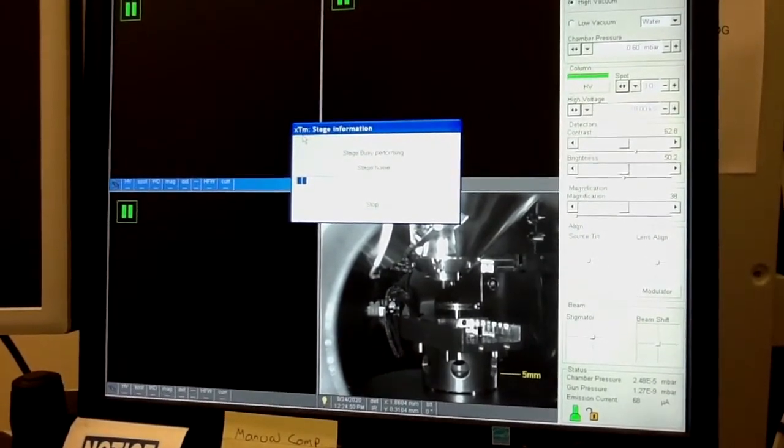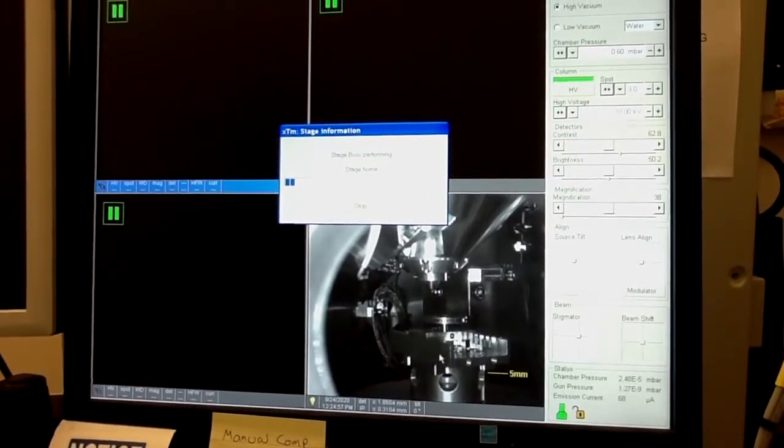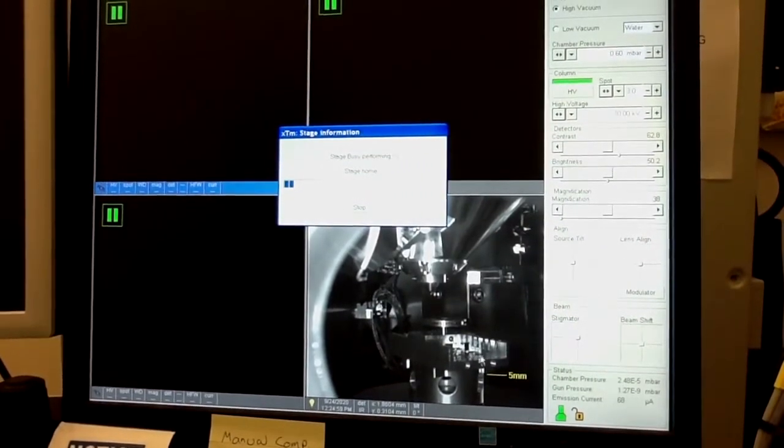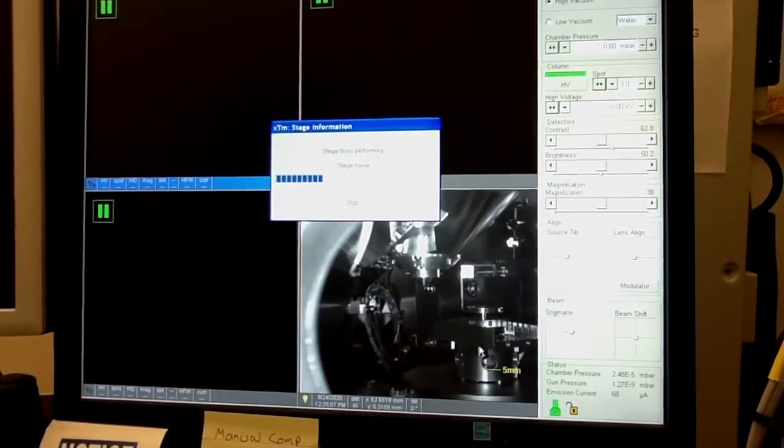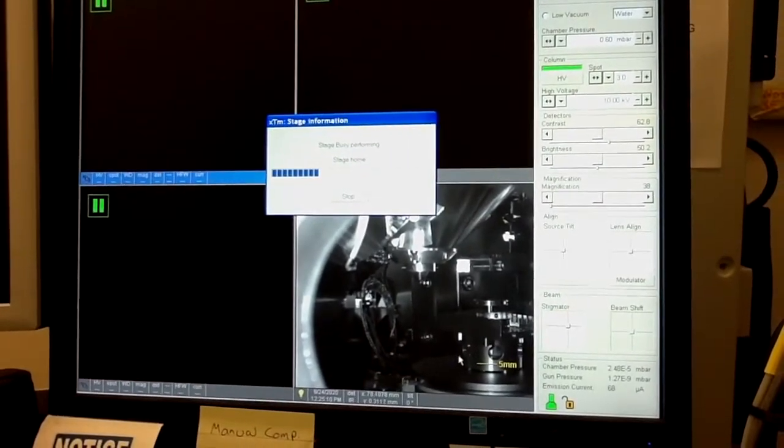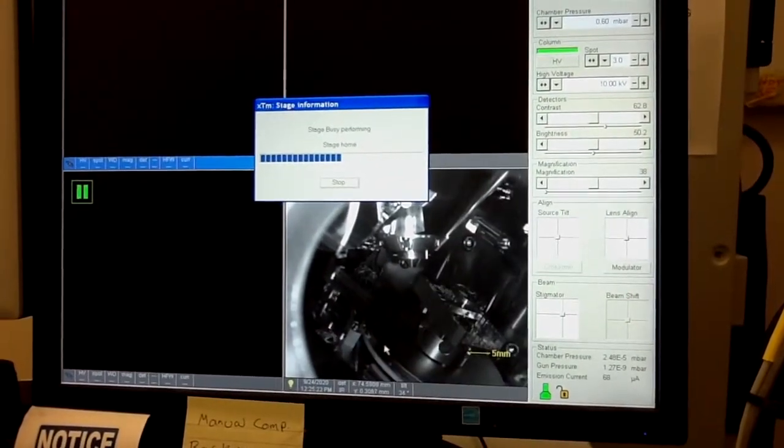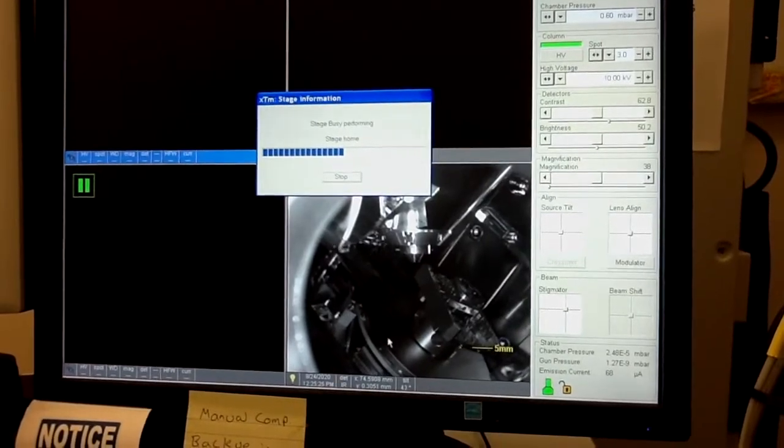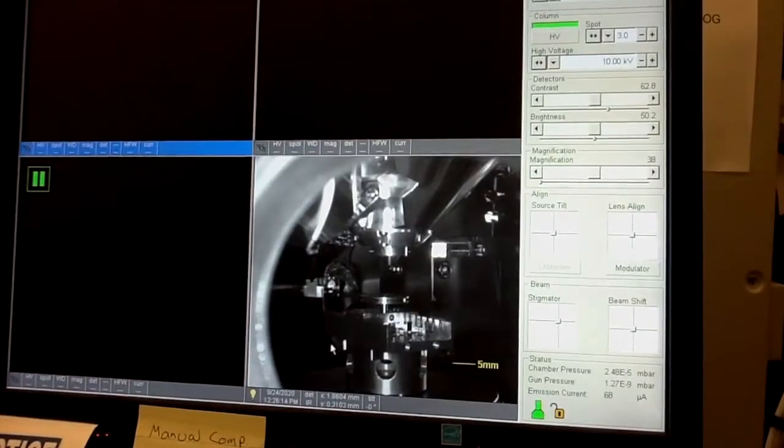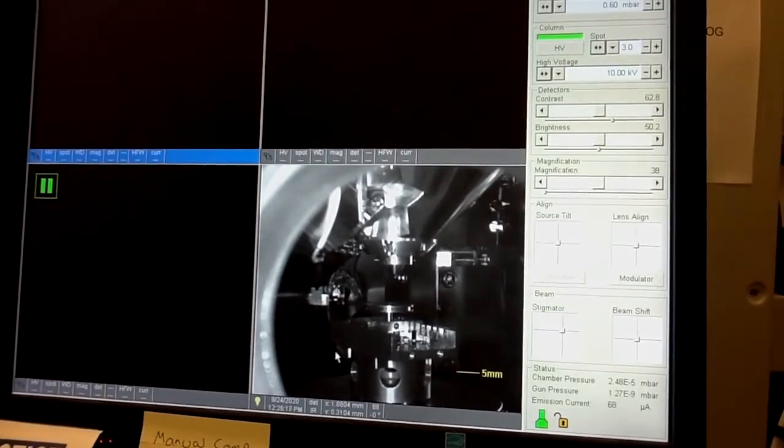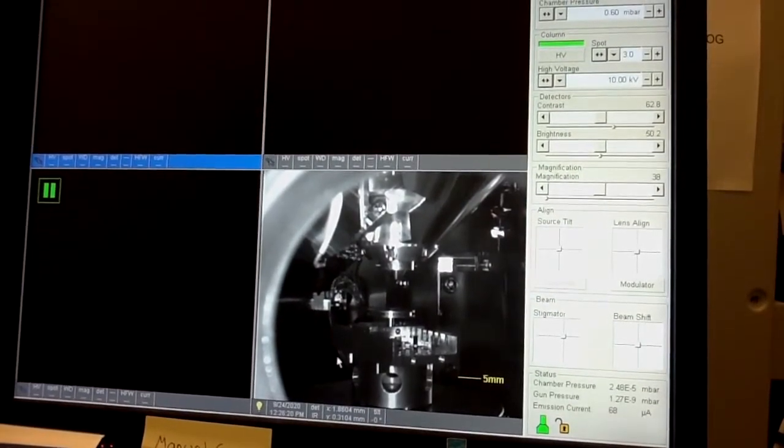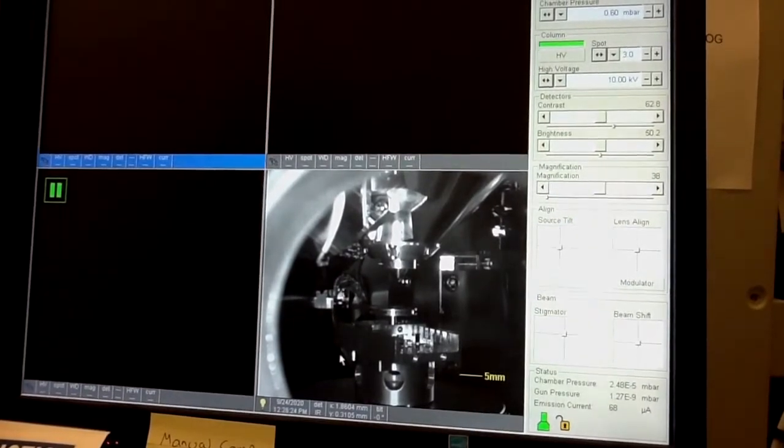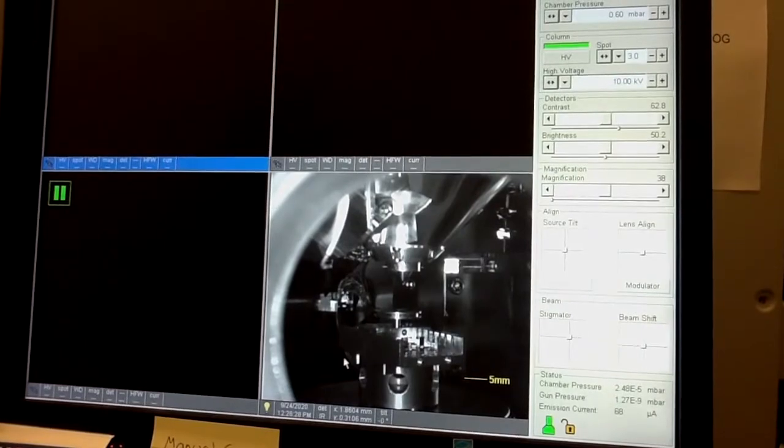Then what you will see here in this, this is the view from the chamber. It shows that the stage goes through some checking points. You will see that checks all the drives moves to the different positions and gets oriented. Once this is done, the system will know exactly what's the coordinates of your samples and the stage. You have to do it. Otherwise, you will not be able to move the stage. So you will only be able to look at the sample exactly in one spot, which is very limited ability.